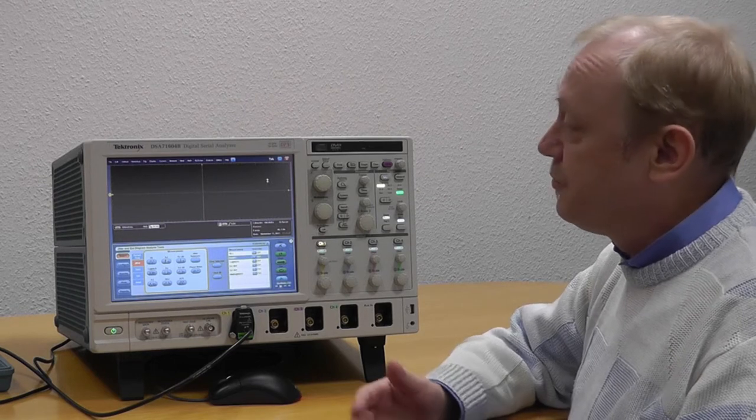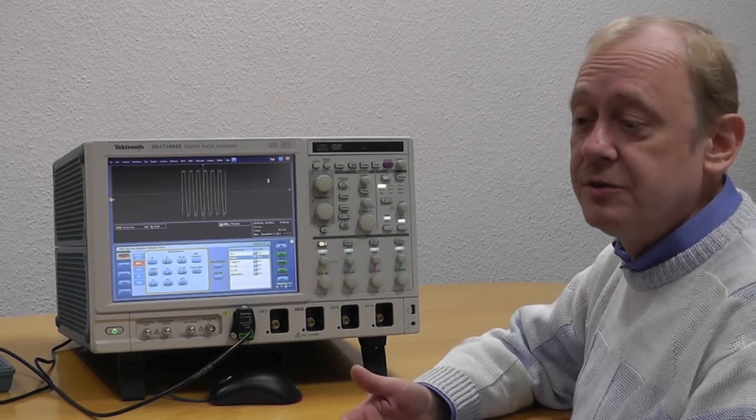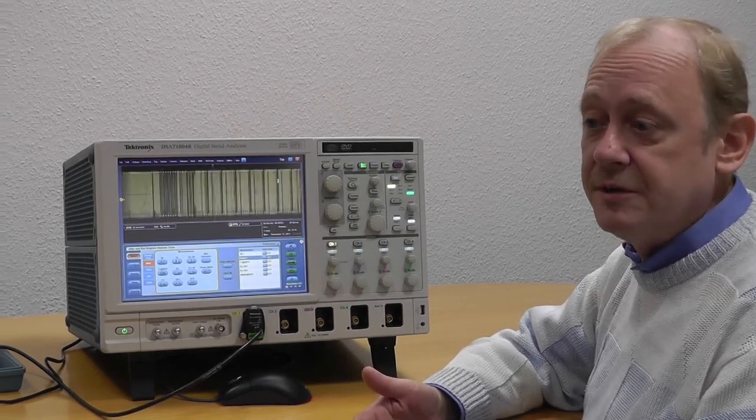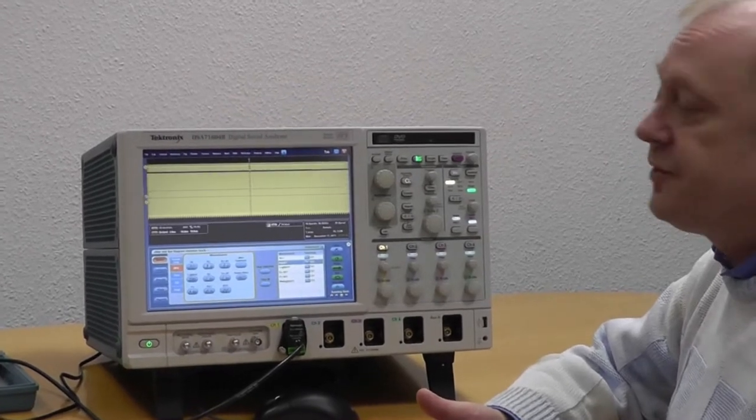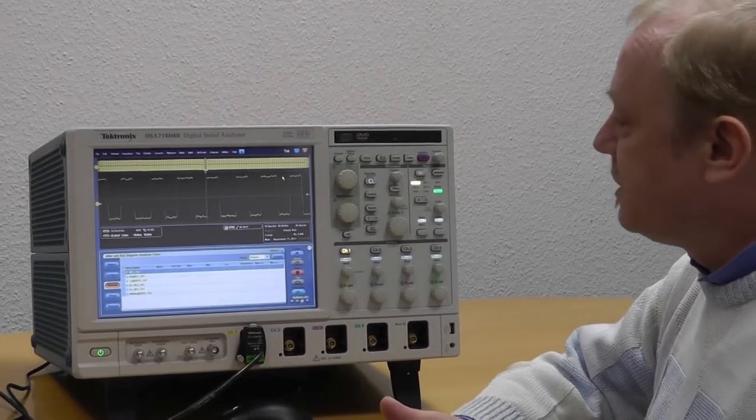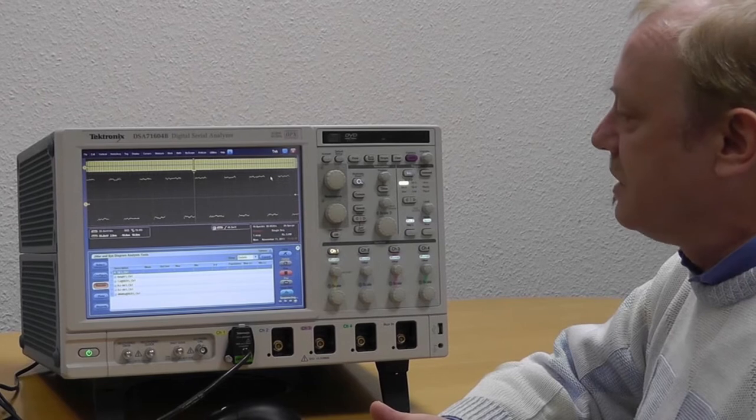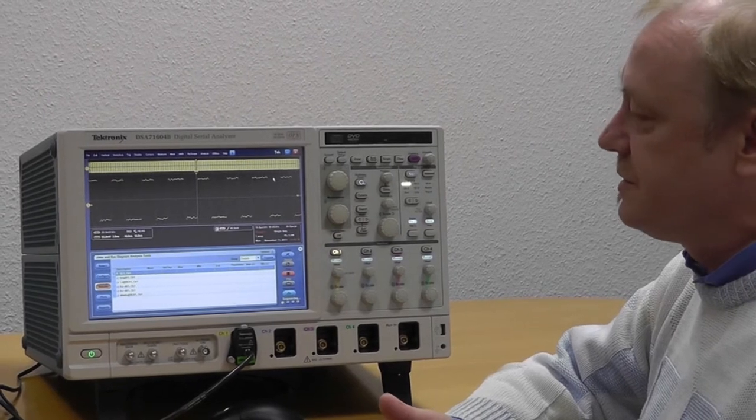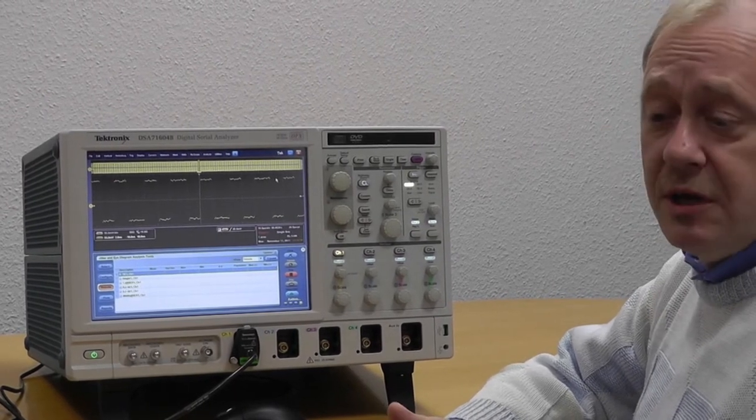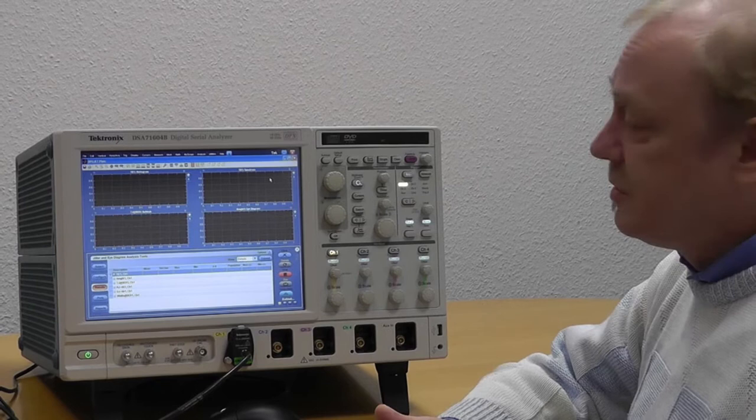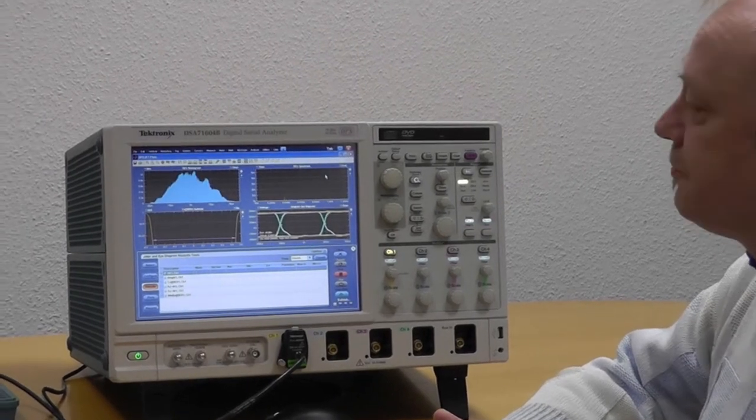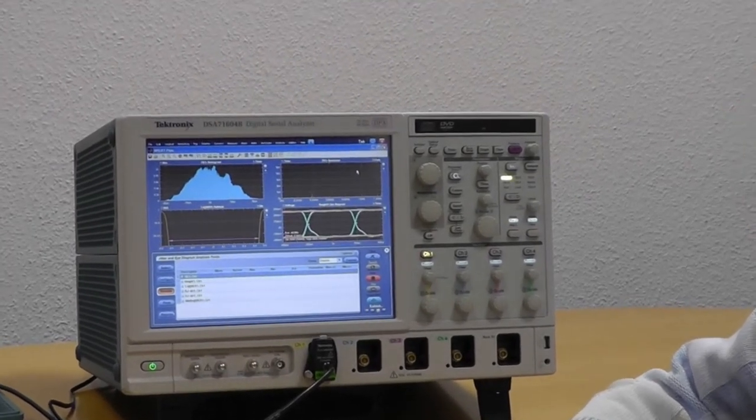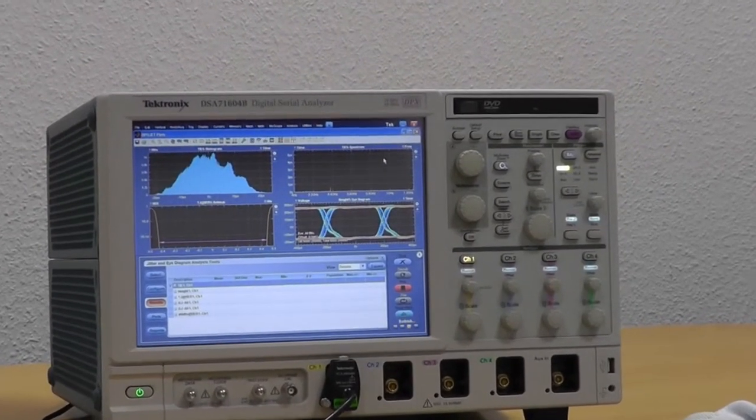It will measure the signal, look to the signal, find out its parameters, and then set up accordingly the right parameters for the scope like sampling rate and vertical size and so on. Additionally, it will find the right measurements and set up DPOJET to make the most important jitter measurements.